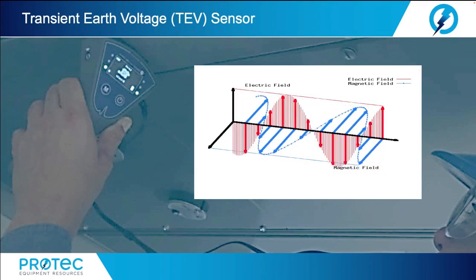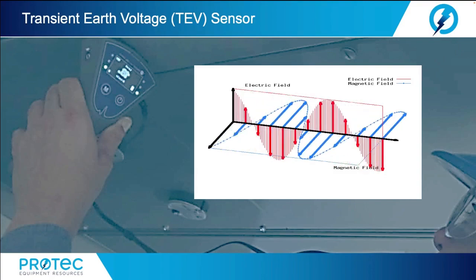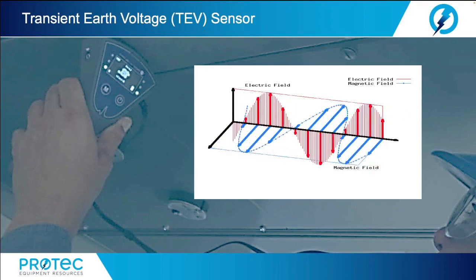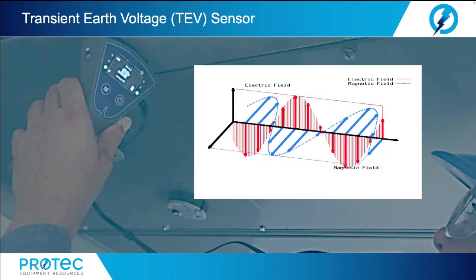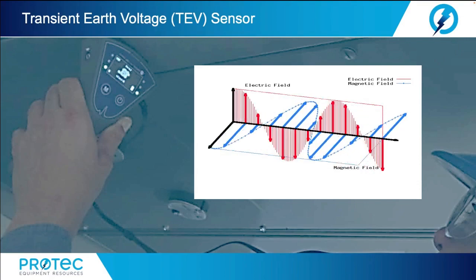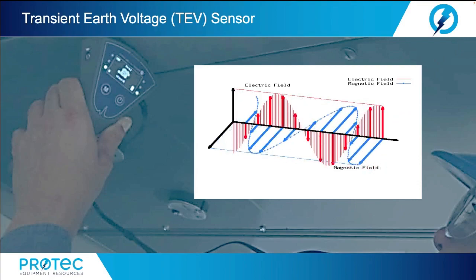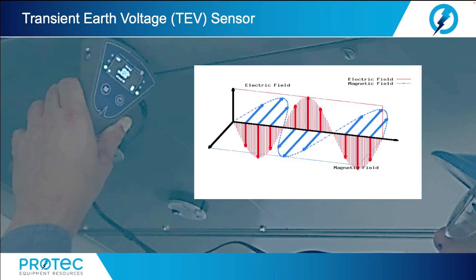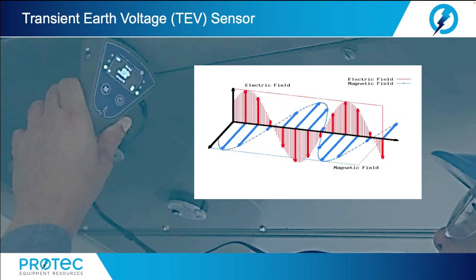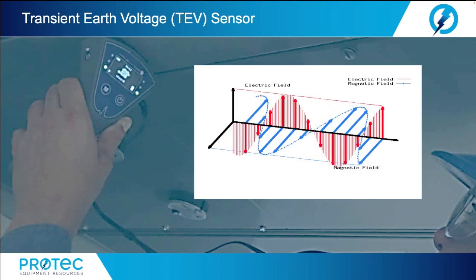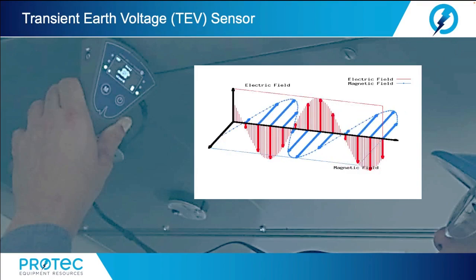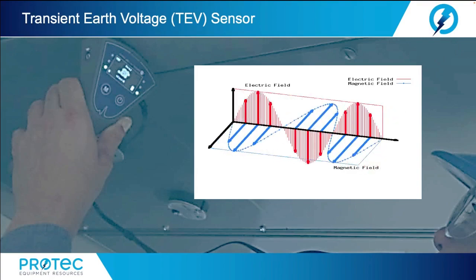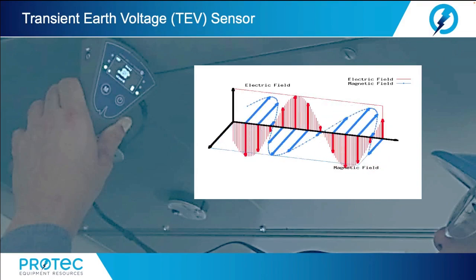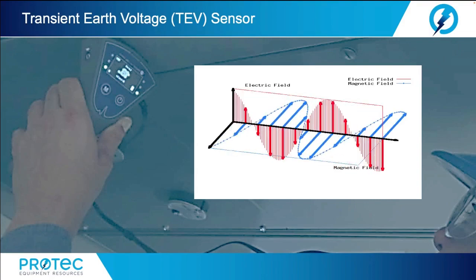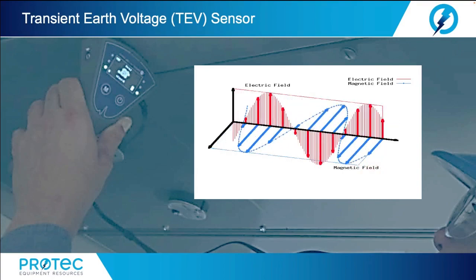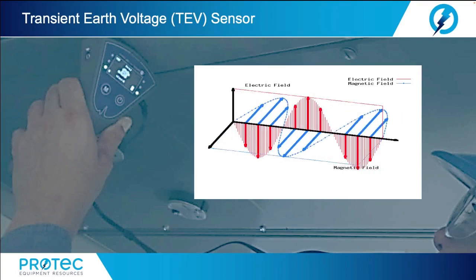Void type PD will typically not generate much TEV range signal. Also, PD inside of fluid dielectrics such as transformer oil will not produce a detectable TEV signal. It is important to use UHF, high-frequency CT, and ultrasonic sensor data in synthesis with the TEV in order to see the whole picture and draw an accurate conclusion about the asset's insulation health.